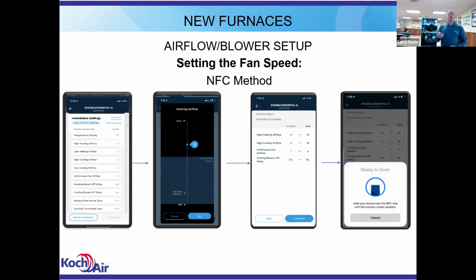All right. So you go in, you make changes, and then you select OK, and then when you select continue, you're going to get a menu that says, hey, here's the changes that you made. That's the way the board's programmed currently. The new value, that's the value that you put in there that you want to change it to. If that all looks good to you, you press continue, you scan it again, and it'll download the information from your phone down to the board.